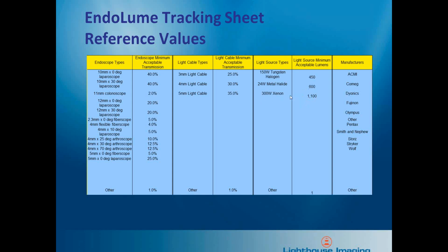If we look at this, let's make it easy and start with 1000 lumens. If we hook a light cable to it and get 35% transmission, just going through the cable we're down to 350 lumens of power. If we then go through an arthroscope that has maybe 10% transmission, we may only have 35 lumens of final power. We'll show those measurements in a demonstration in a moment.